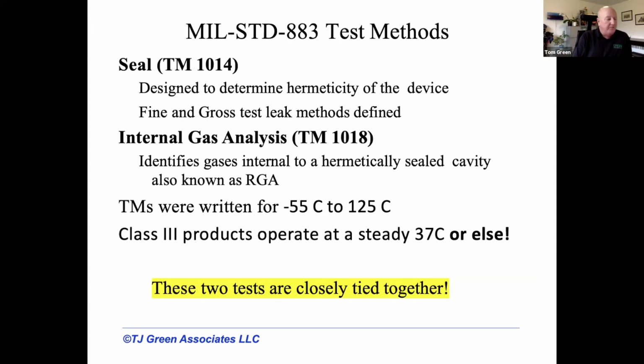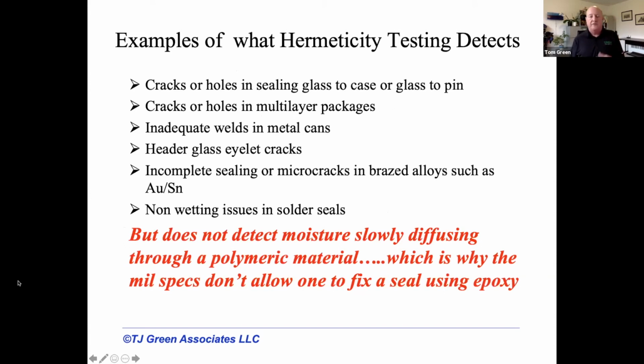So one thing you have to keep in mind, anything that was built to 883 is generally intended to work between minus 55 and 125 C. Yet in the body, it's a pretty benign environment. As a matter of fact, when somebody says the component must have lost hermeticity, I always find that hard to believe, because it's the same technology. They're hardened ceramic or glass-to-metal matched feedthroughs. And the body really is relatively benign, but these two test methods are closely tied together when you start to think about how long I can expect my implanted device to last in vivo.